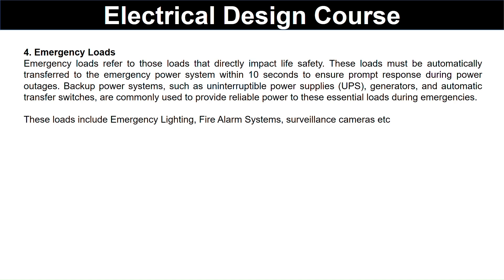Emergency loads refer to those loads that directly impact life safety. These loads must be automatically transferred to the emergency power system within 10 seconds to ensure prompt response during power outages. Backup power systems such as UPS, generators, and automatic transfer switches are commonly used to provide reliable power to these loads during emergencies. These loads include emergency lighting, fire alarm systems, surveillance cameras, etc.